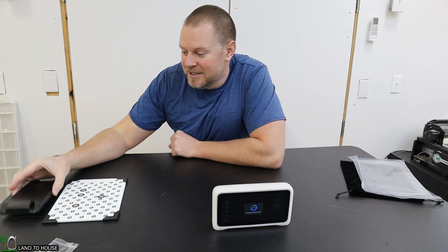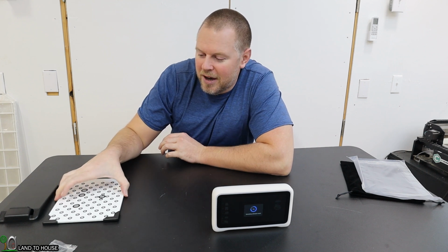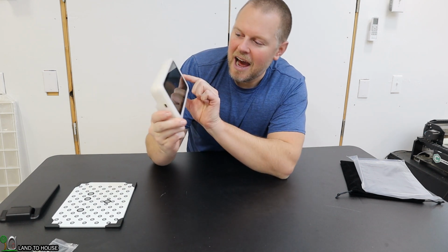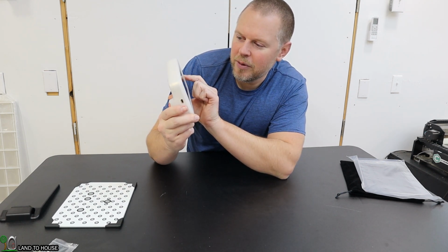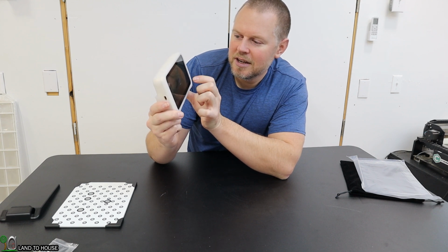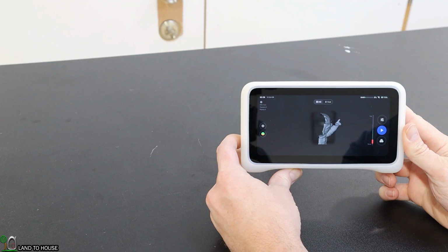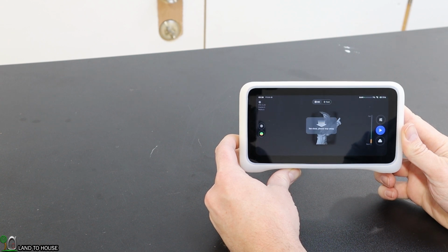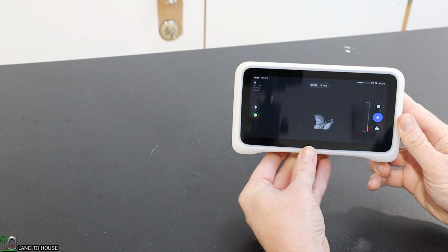Okay, the first one was fun. By the 8th one, it was a headache. So having to do that every 3 days is going to be unpleasant. However, I think the results from this scanner are going to be worth doing that so frequently. And I also imagine the more I do it, the better I will become at scanning this plate. So, all right, currently it said it was gathering the data and generating. Calibration succeeded. All right, it's applying that calibration. Looks like calibrating this unit took right at 25% of the battery, so it certainly is going to be a battery hog.